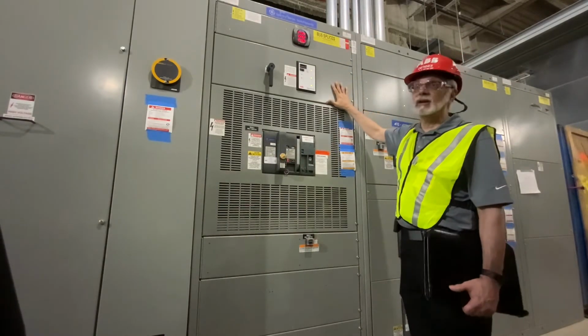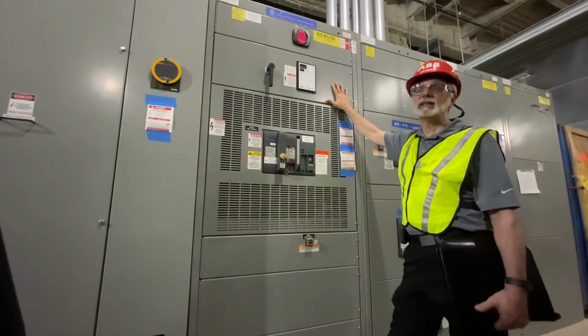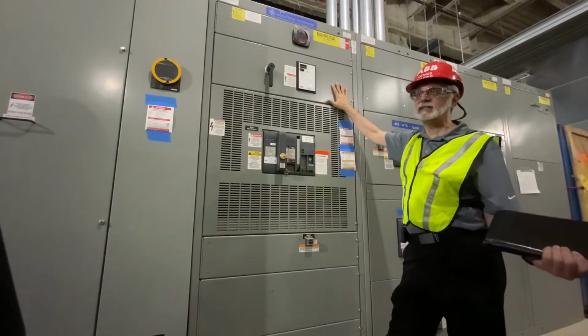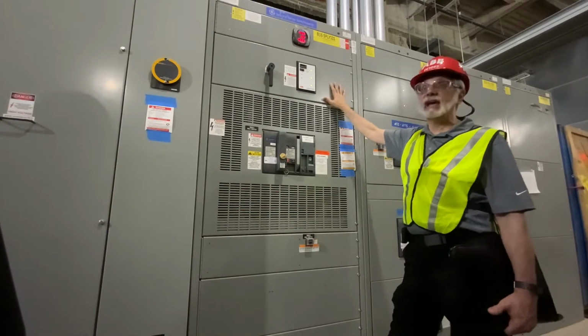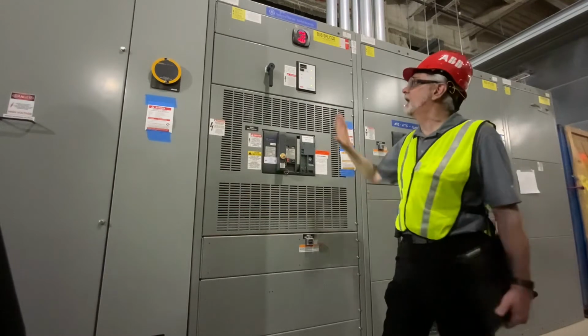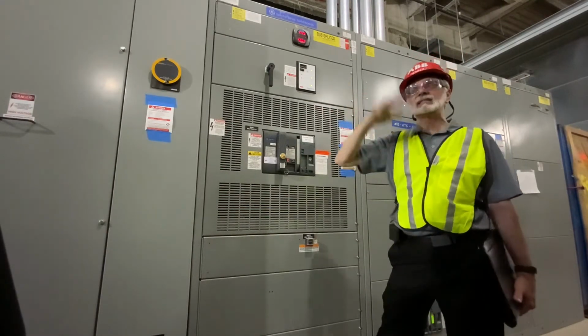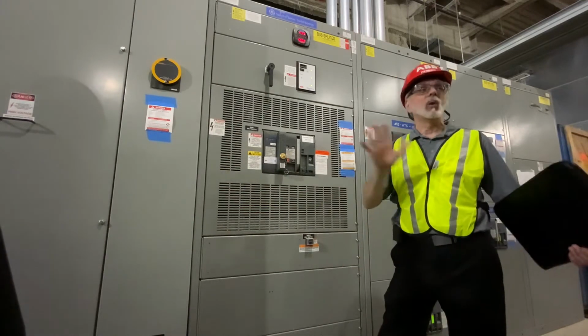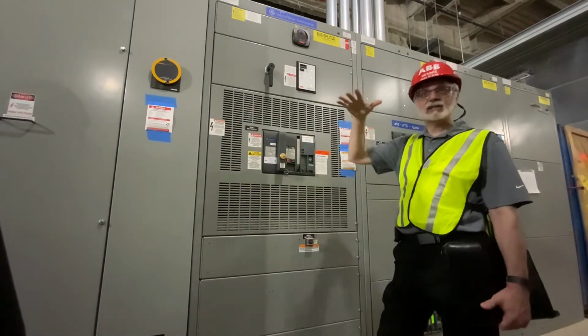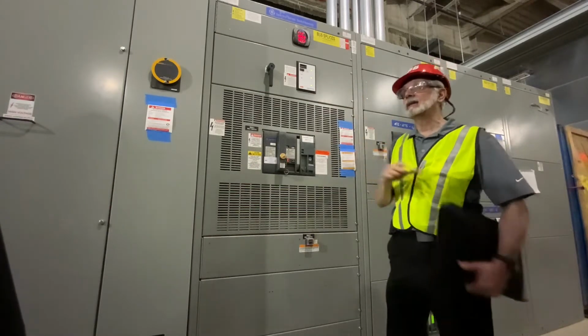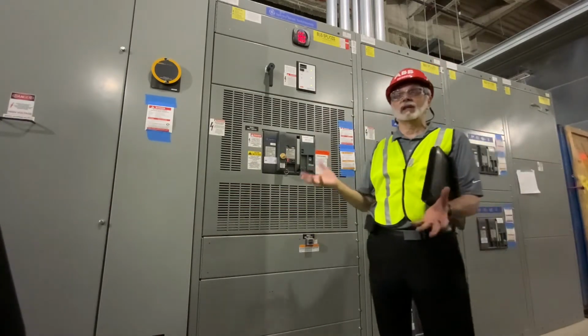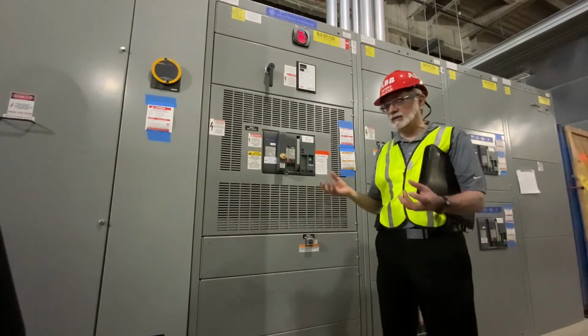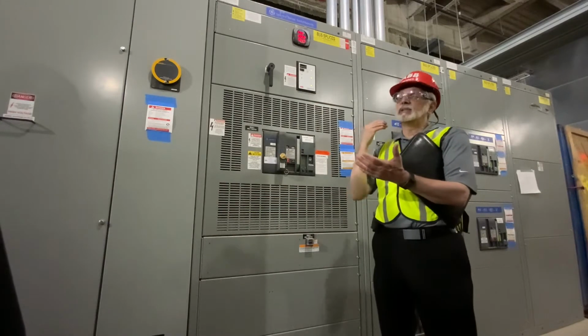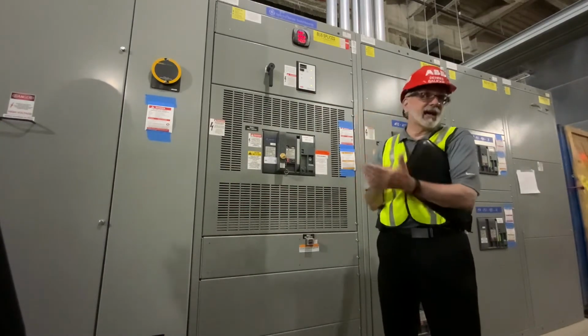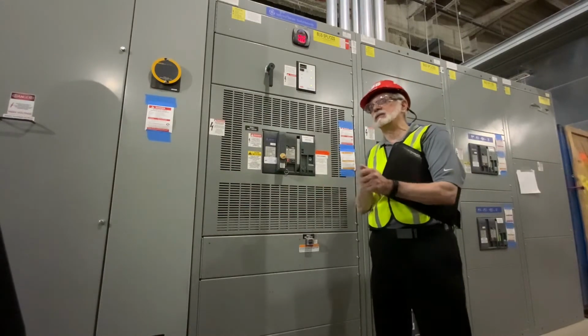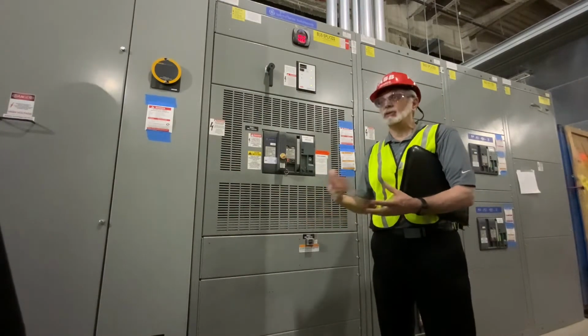The next device down here is the surge protective device, or SPD. In the old days, we called them TVSS, transient voltage surge suppressors. This is in case you get any kind of surges on the line. This will dampen those down, so sensitive electronic equipment downstream won't be affected. Where this is really more practical from your standpoint is you probably have some large chillers in this building, and a lot of people don't talk about it, but switching transients from turning the contactors on and off on chillers is a main contributor to transient voltage.